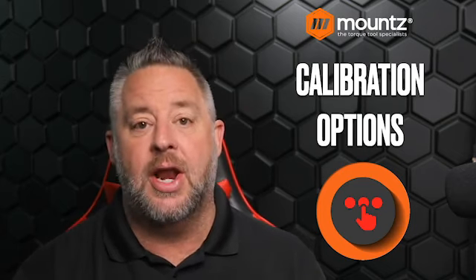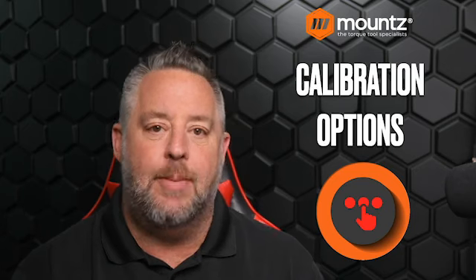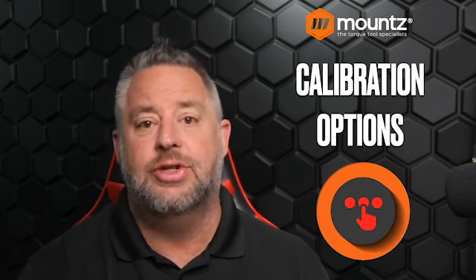So what calibration options do you currently have at your disposal? There are about three that you can use. One is you take your sensors and analyzers and they get sent out to an outside calibration lab, or they can be sent back to Mountz if you're using a Mountz product. Currently, Mountz has three labs. We have one in San Jose, California, one in Foley, Alabama, and one in the UK. So you can send those out to us or to any other calibration facility, and those analyzers and sensors can be calibrated. You can also have a mobile calibration company come into your facility and do the calibration on site.